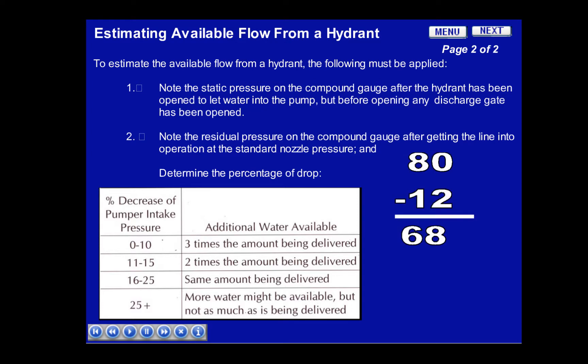In this case, we'll use 80 as our static pressure. After we supplied one fire attack line, we noticed a drop in our intake pressure of 12 pounds, which left 68 PSI as our residual pressure.